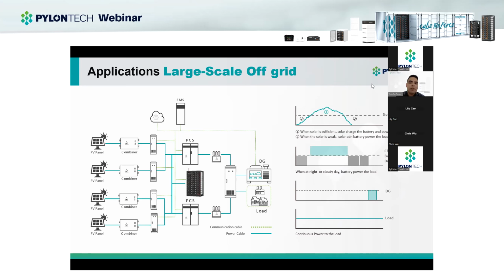When we have solar production, it goes to power the loads and also charge the batteries. When solar production goes down or it's night, the batteries get into the system. For this system, we always have to power the loads. If the system also has a generator, it can be the third priority, used when we don't have solar production and the batteries are at a low state of charge.